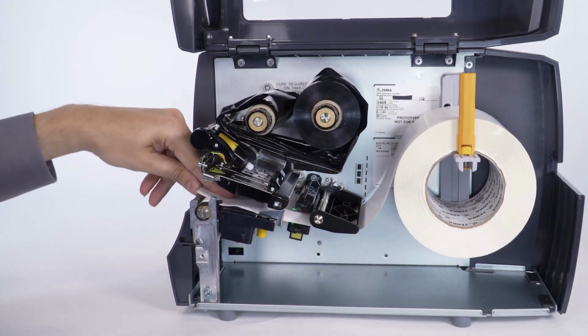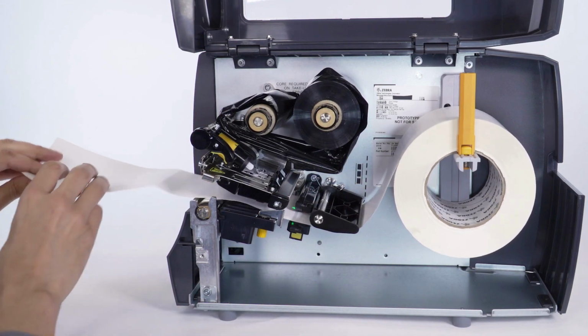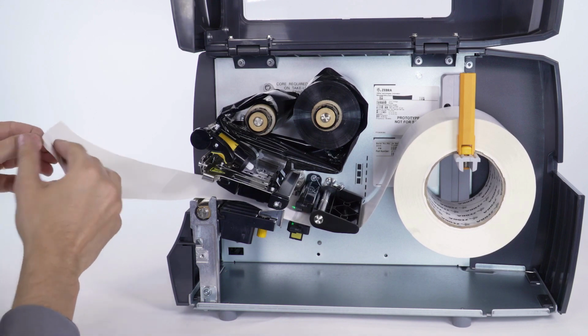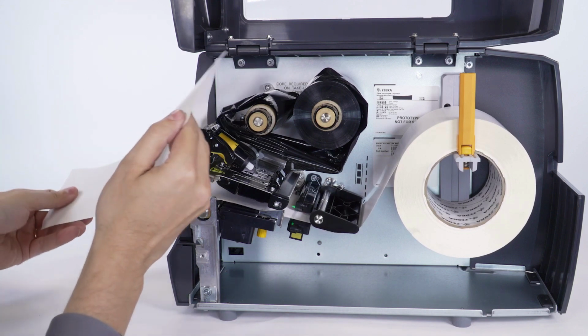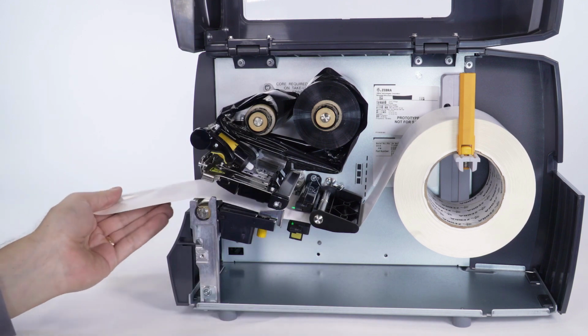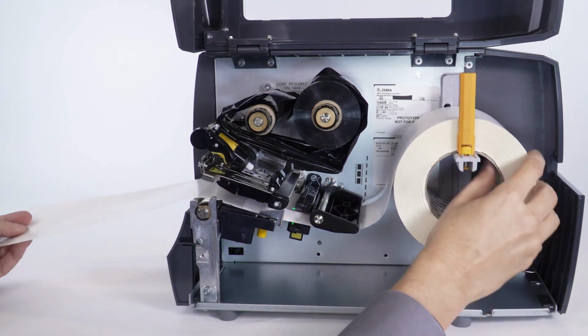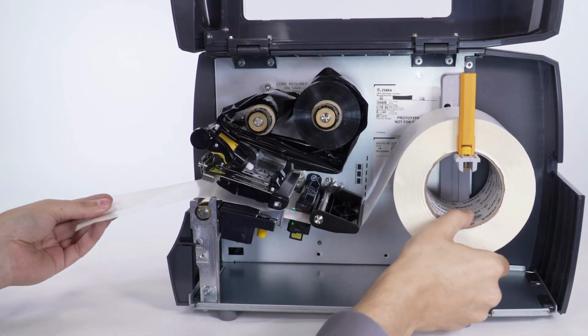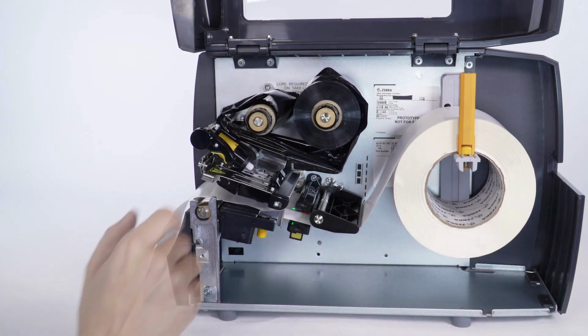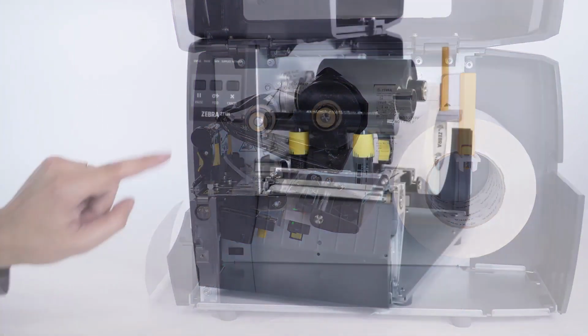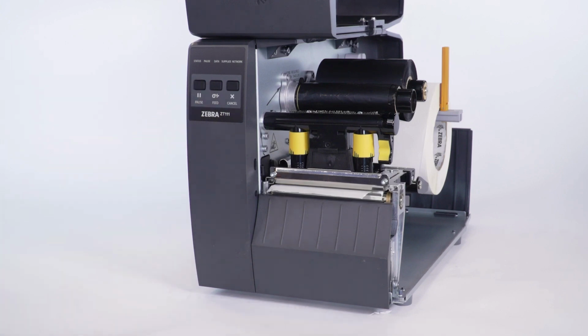Extend the media approximately 8 inches, 203 mm, from the printer. Remove about 6 inches or 150 mm of labels from the label backing. Move the backing until it is under the media sensor. Close the printhead. Press pause. The supplies light will flash while the printer calibrates to the media.